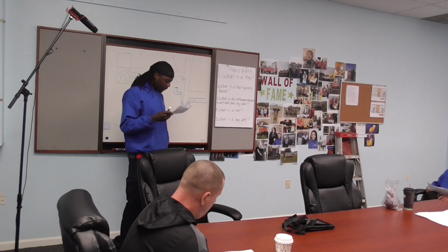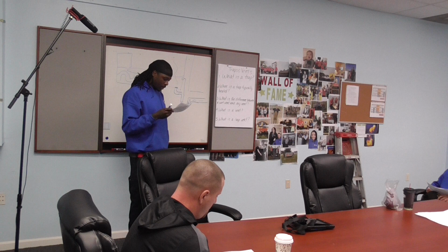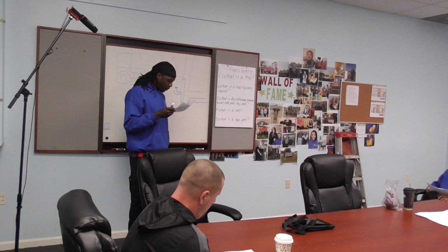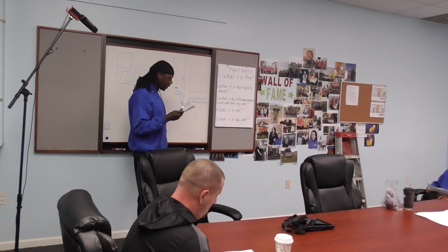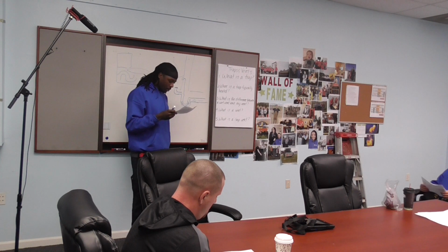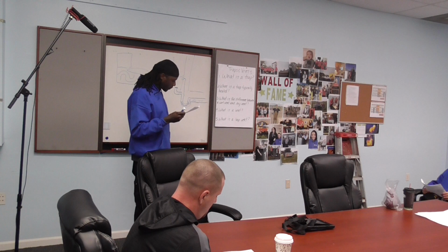Because of its shape, the trap retains some water after the fixture's use. This water creates an air seal that prevents sewer gases from passing from the drain pipes back into the building. Essentially, all plumbing fixtures, including sinks, bathtubs, and showers, must be equipped with either an internal or external trap. Toilets almost always have an internal trap.